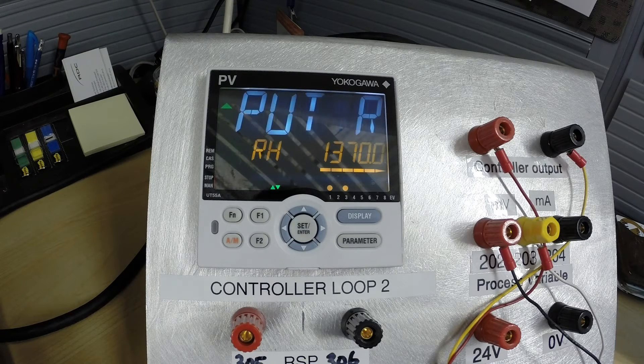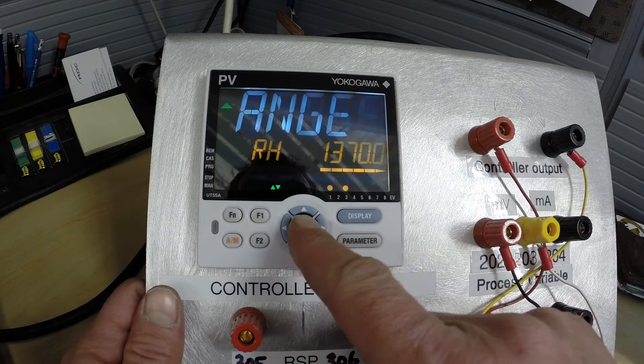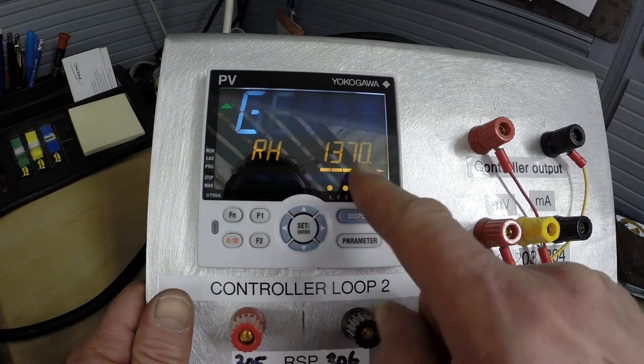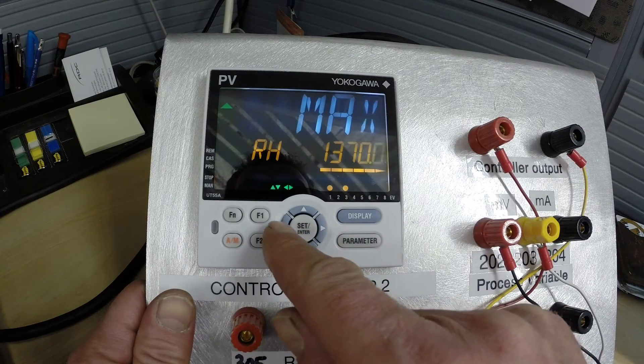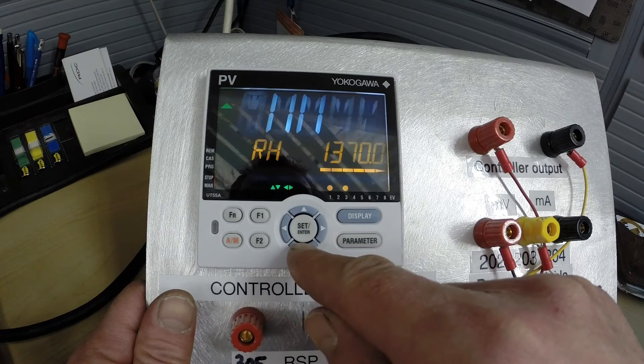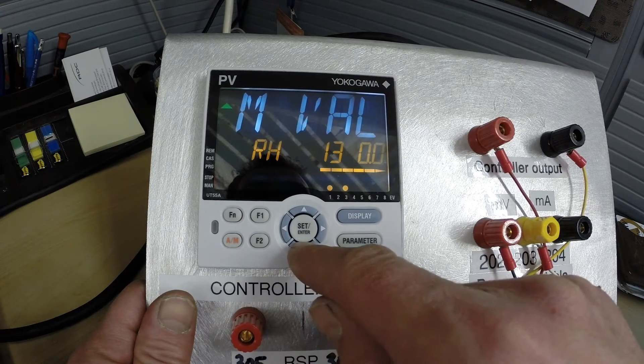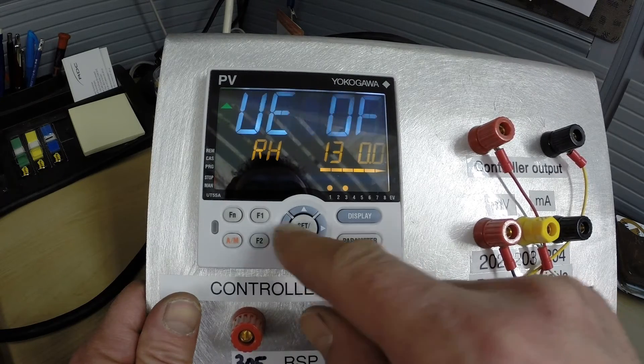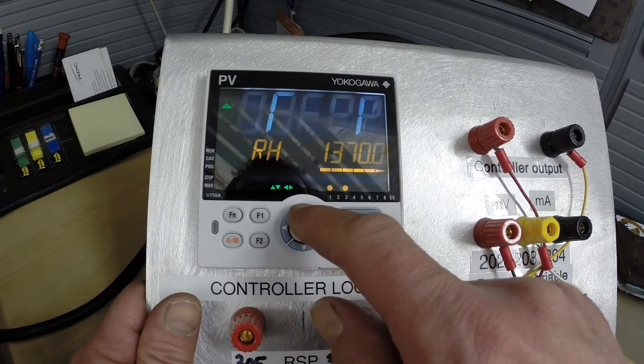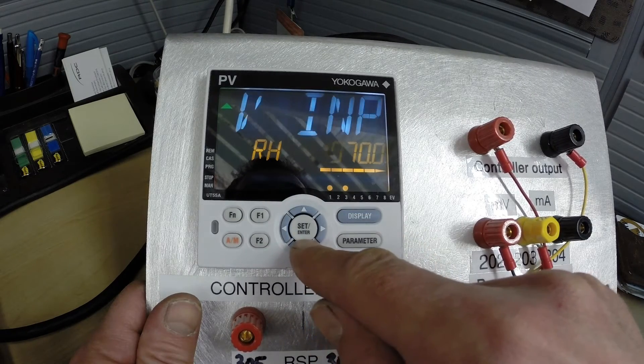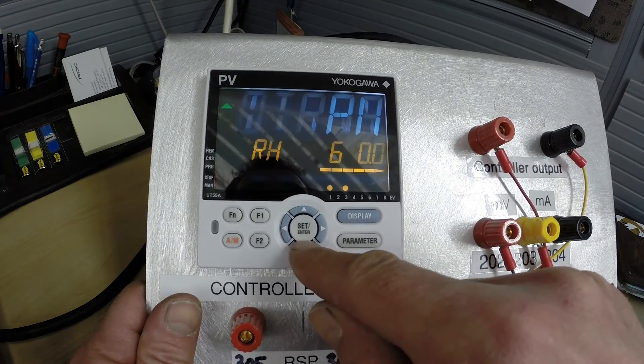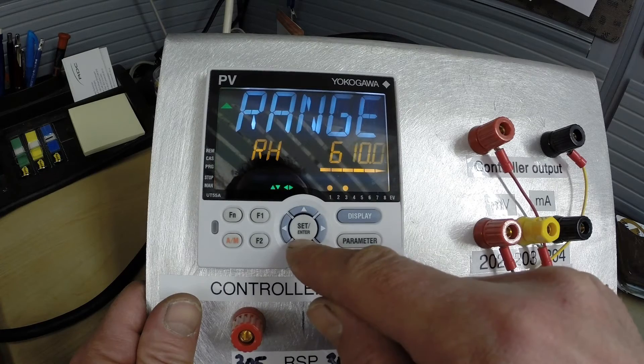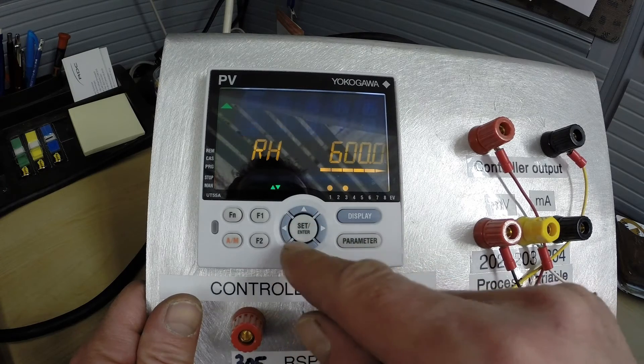But we are going to change this for the sake of this lab to an operating range that we can work with. So we're going to pick range high of 600 degrees. So in order to do that we will press the set button and we simply move left or right to get to the correct position and the up or down arrows to set it. We will just quickly set this to 600.